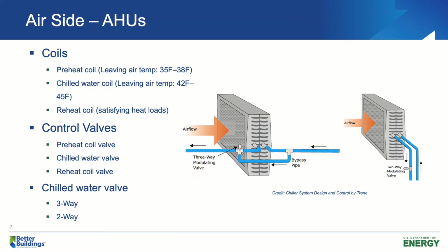This way, the coil will have less flow to match the cooling load, but the main pipe will have the same amount of flow all the time. Therefore, for 3-way control valves, when the cooling load drops, we will not have any pump energy savings. However, for 2-way control valves, when the cooling load drops, we can simply close off the 2-way valves a little bit. This way, we will have less chilled water flow both inside the main pipe and through the coils. We can save a lot of pump energy from using 2-way chilled water control valves.